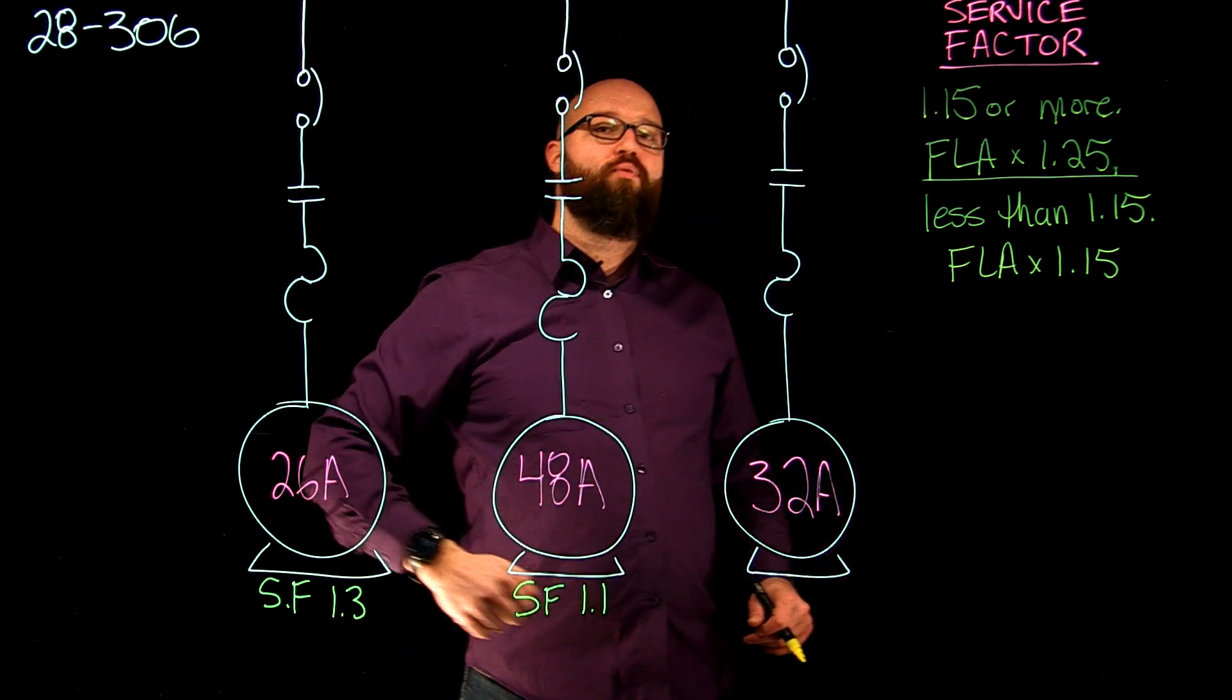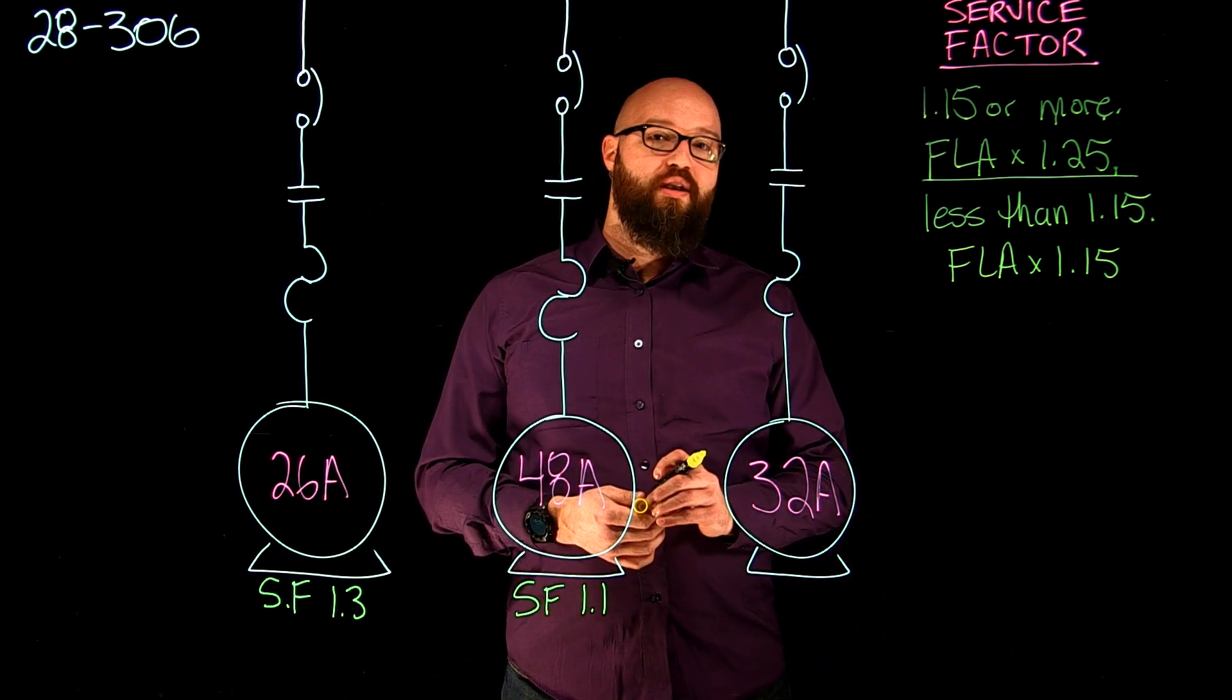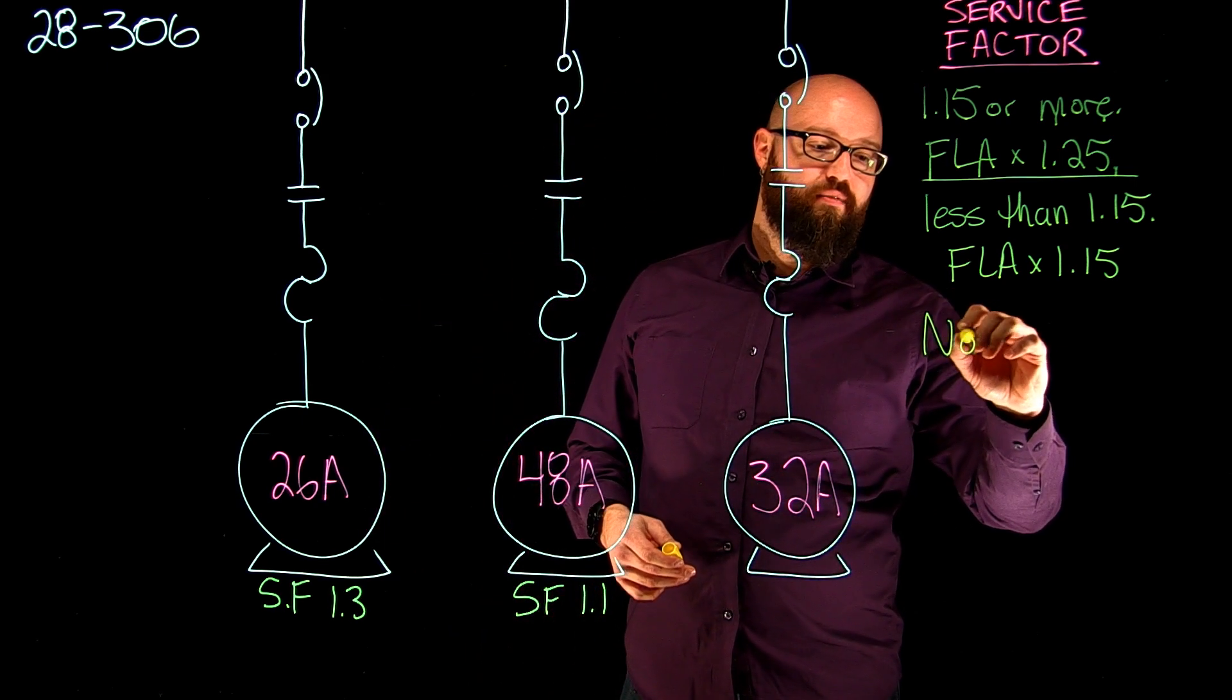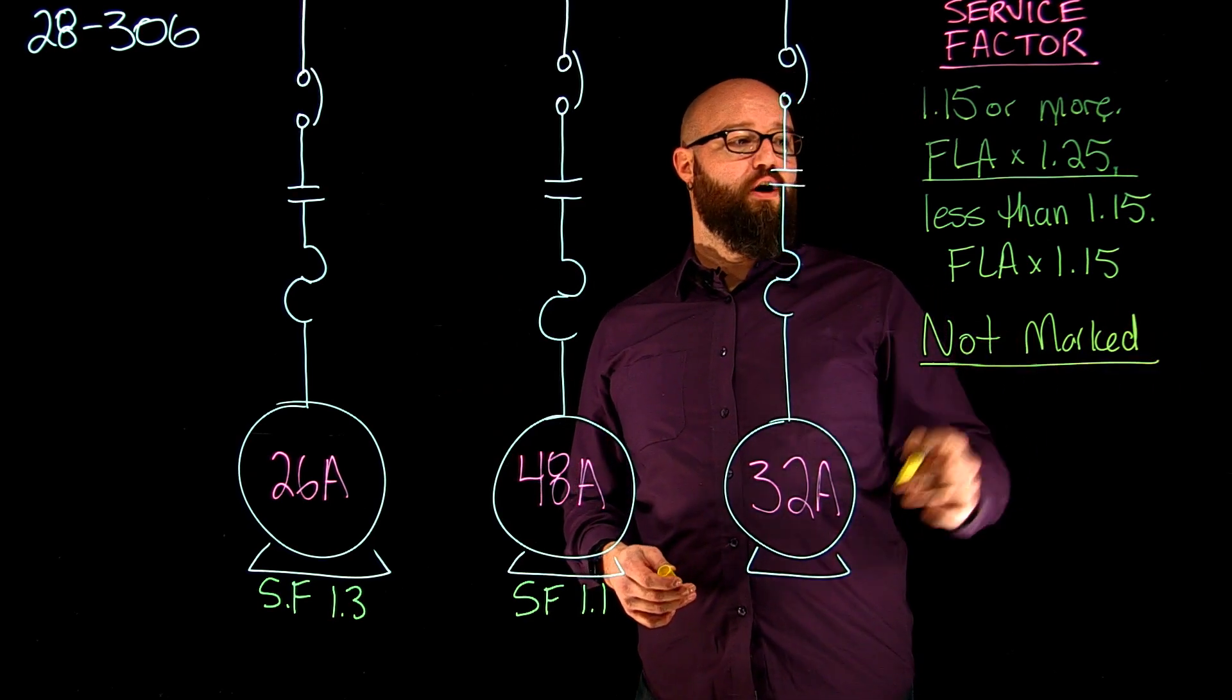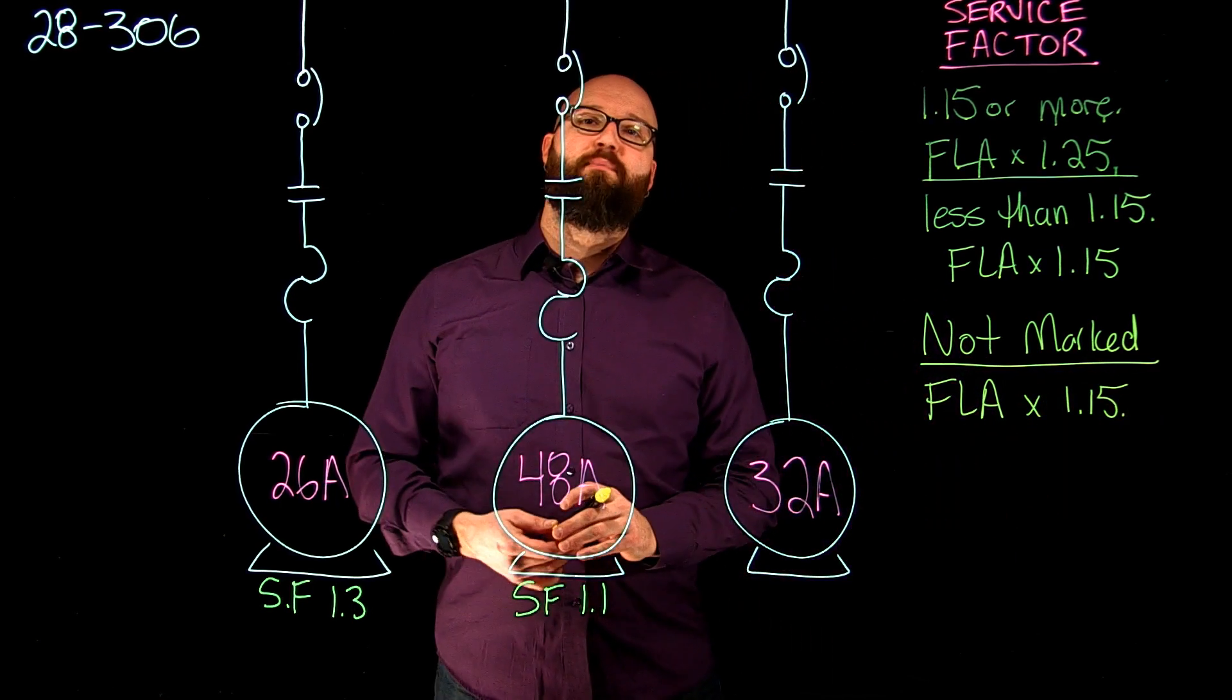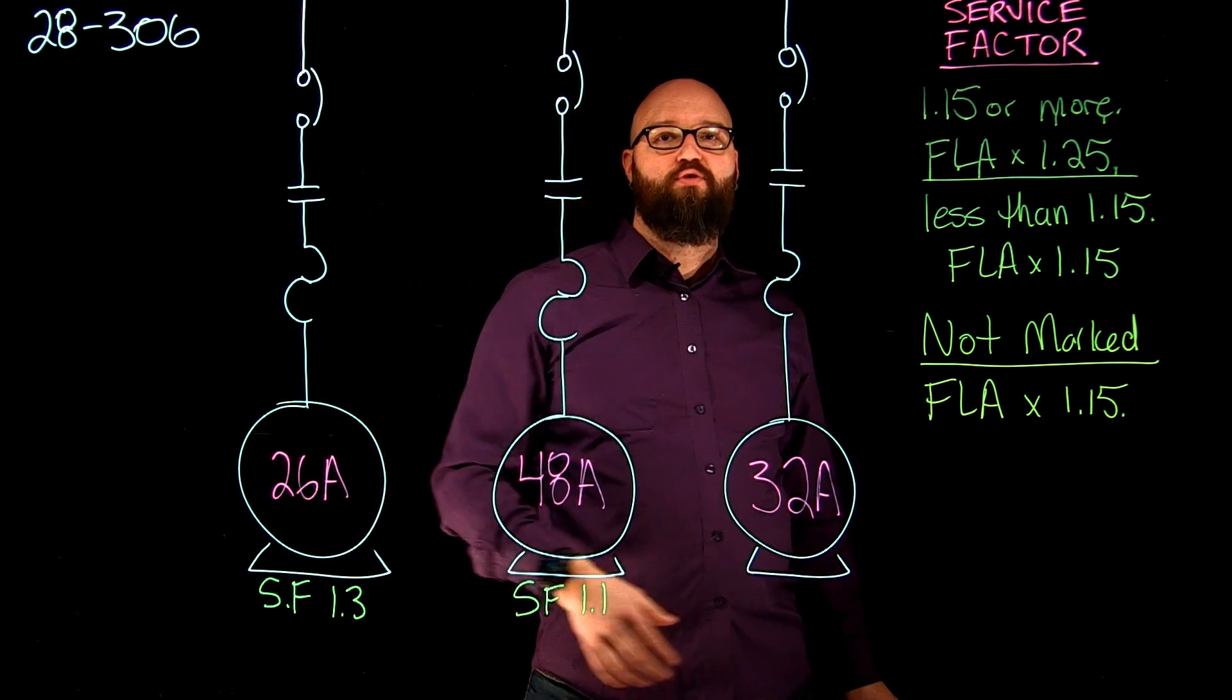So what do we do if we don't have a service factor marked? We would assume that this motor has a service factor of 100% or 1 at this point, and then it falls into the category of less than 1.15. So if it is not marked, we're going to go FLA times 1.15, and again that would give me the maximum rating or setting of my overload device. We're going to take this from 28306 and apply it to our three individual motors here.